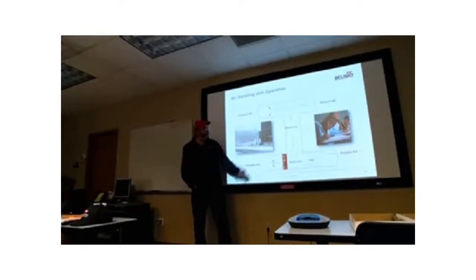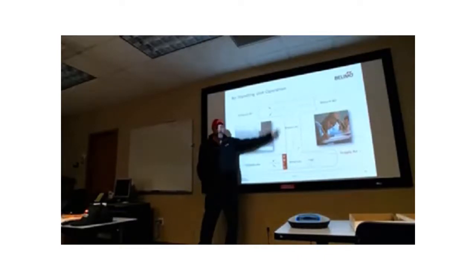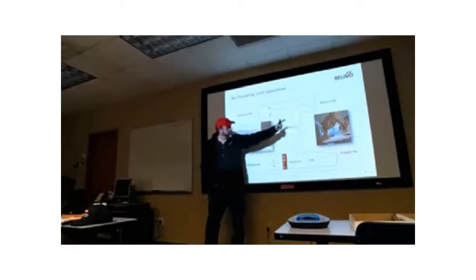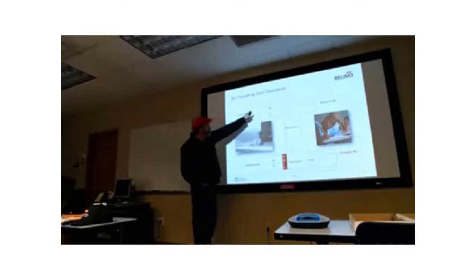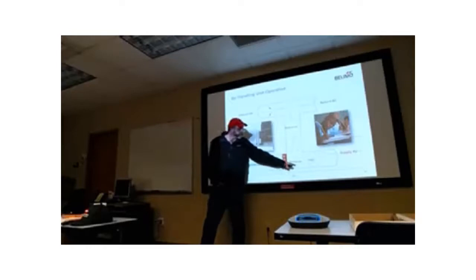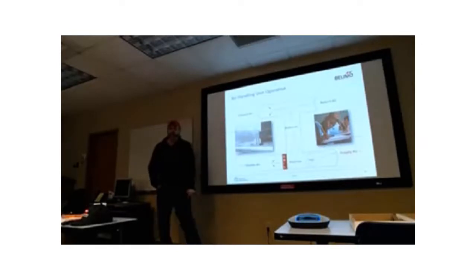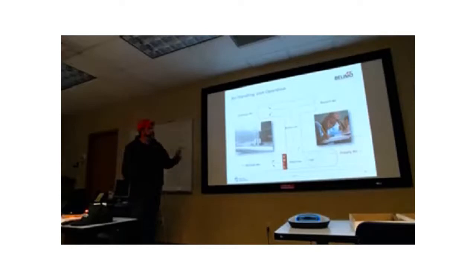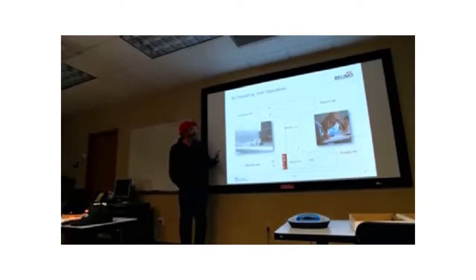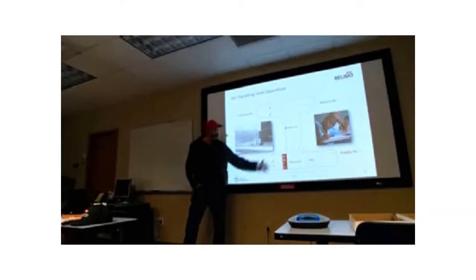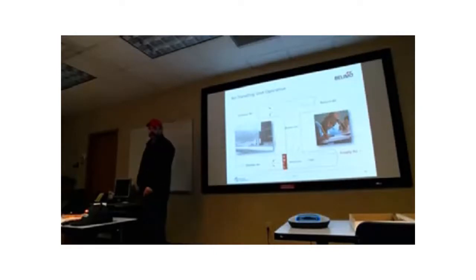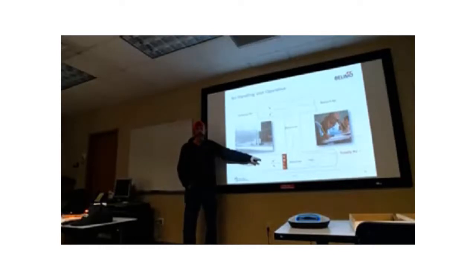Yeah, you could, normally that would be in this one though, right? It would be an exhaust air. One in each. Yeah, and you could actually transfer, right? So this is a preheat coil technically, or it could be outside air comes in this way, goes out to the space after it mixes with return air comes back, either circles back to the suction side of the fan or it goes out over the side. So if you were designing this system and you talked about failsafe, which one of these dampers would be failsafe, if any, and why would they be failsafe? So outside air would be what? Failsafe, and fail what? Open or closed?